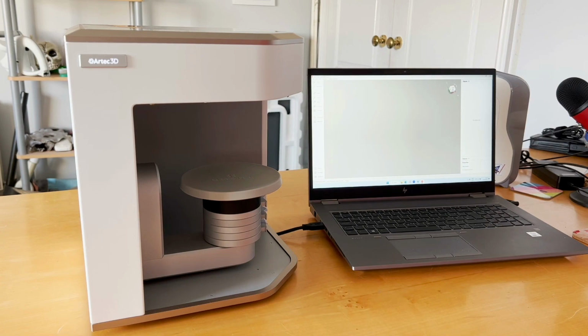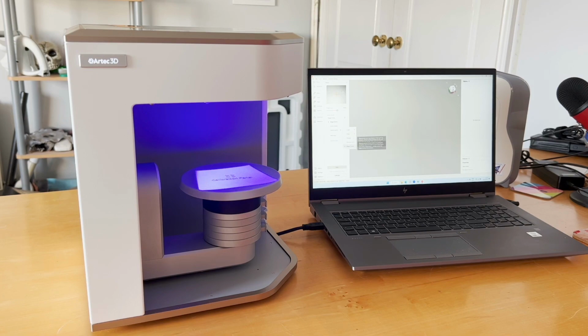And what we can do now is we can actually use this lid as a little test. So if you say you want to do scan, then from the drop down different options you can adjust first the contrast. So you need to adjust the contrast so there's no red dots shown in the picture. Then you can choose from one of the presets, single scan. And then you've got the option here to say scan.